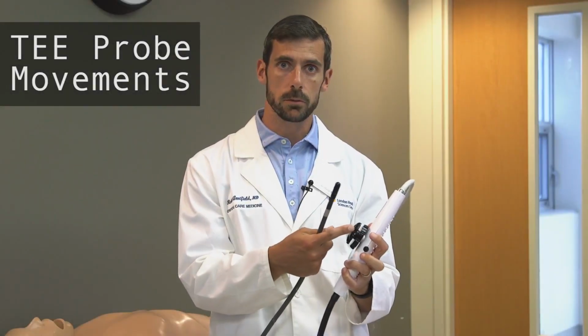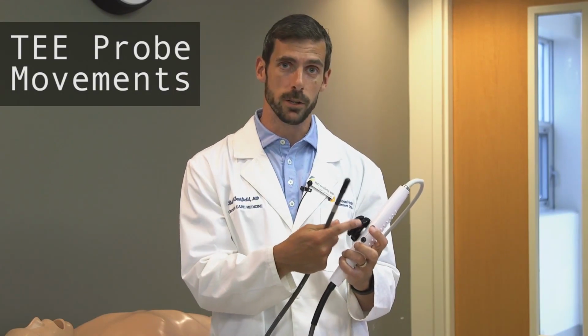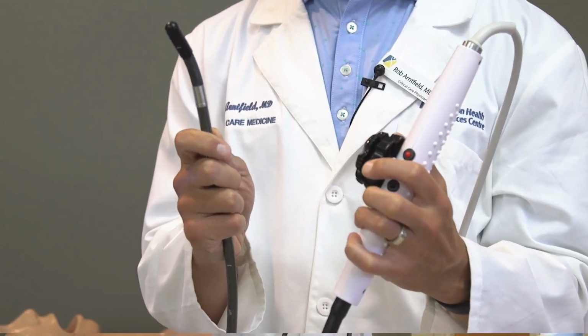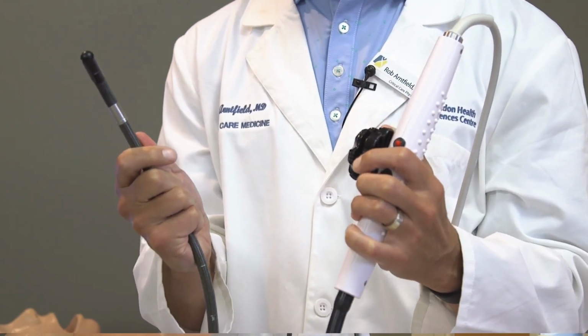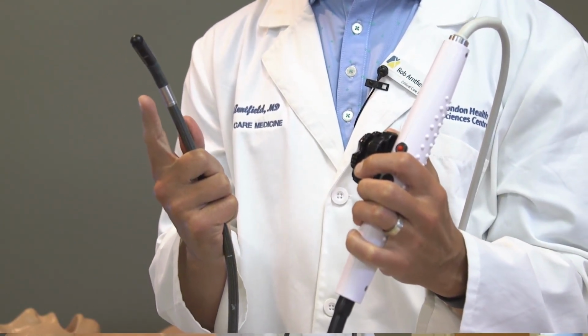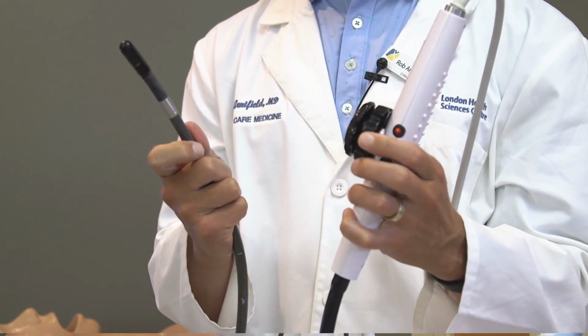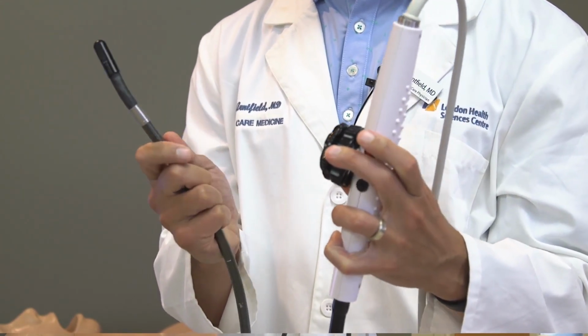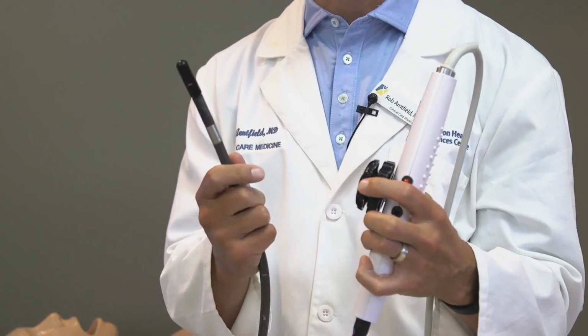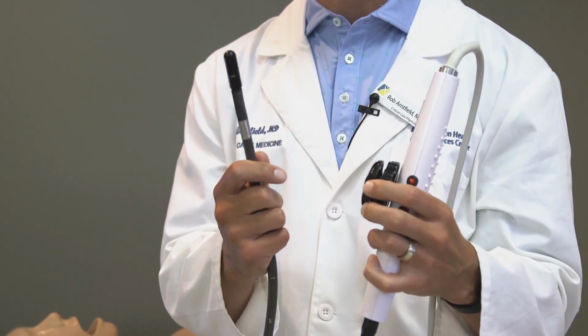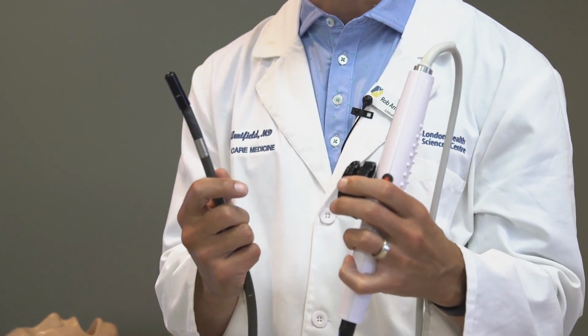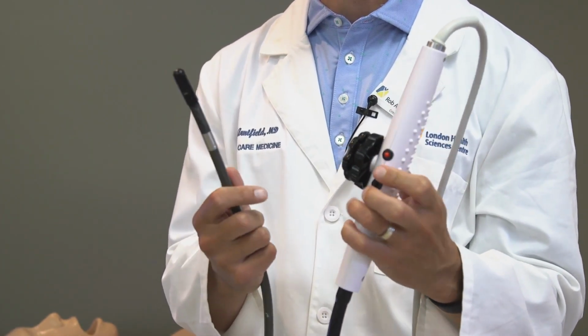The two wheels, technically we just call them the big wheel and the small wheel. The big wheel, which is the one you'll use most commonly for goal-directed TEE, will control flexion of the transducer in the anterior and posterior planes. You'll see here that clockwise rotation results in what's called anteflexion, the folding of the ultrasound crystal face towards the probe, and counterclockwise movement will result in retroflexion. The small wheel controls lateral flexion, which you can see moving side to side, used generally less frequently than the ante- and retroflexing features.